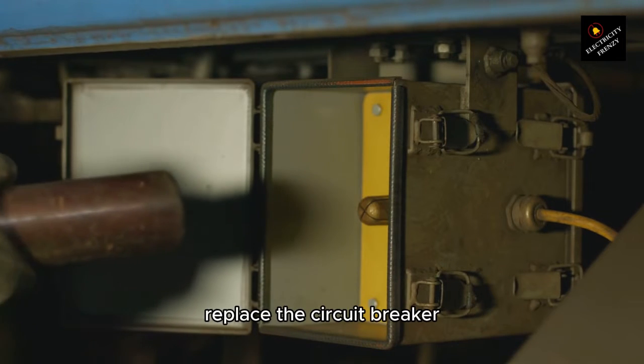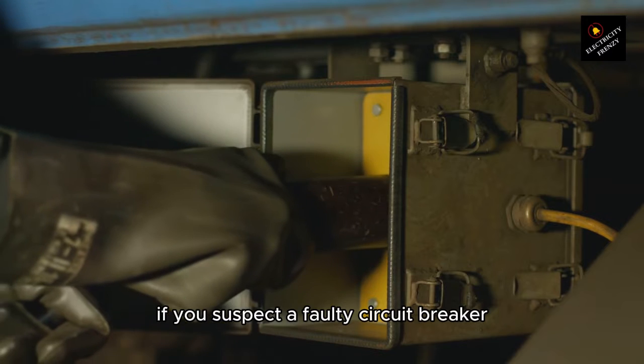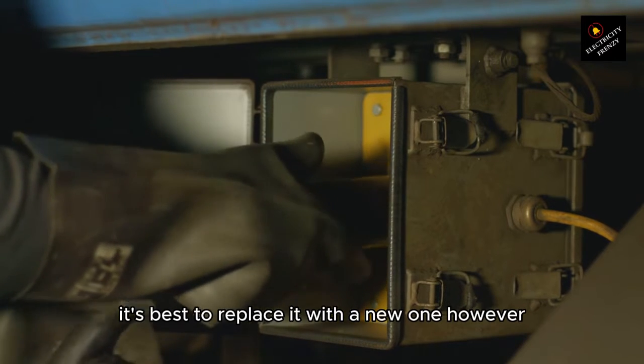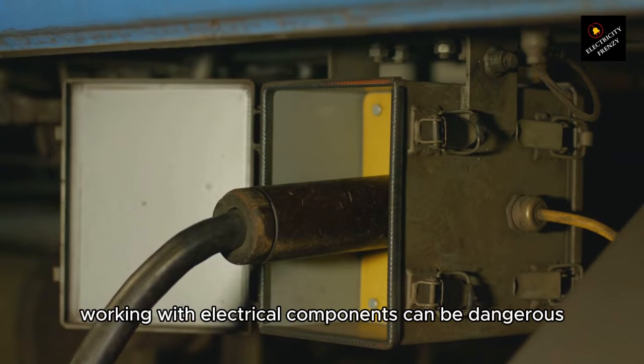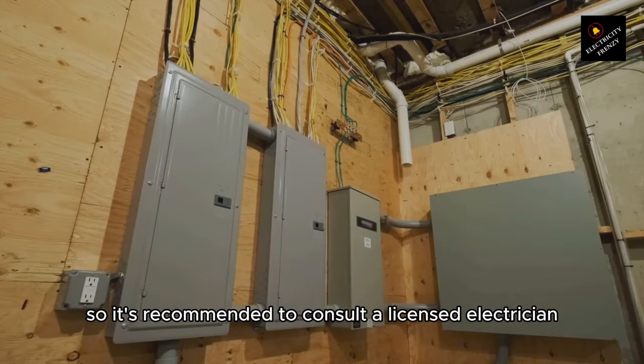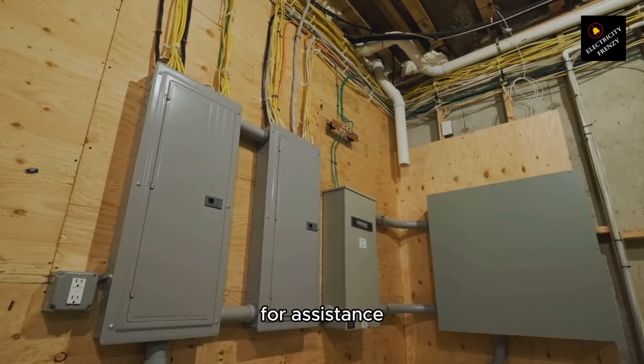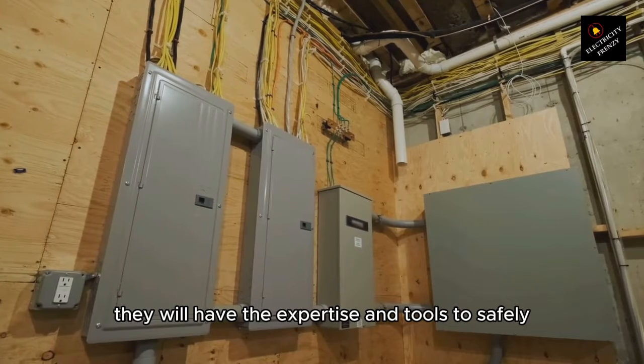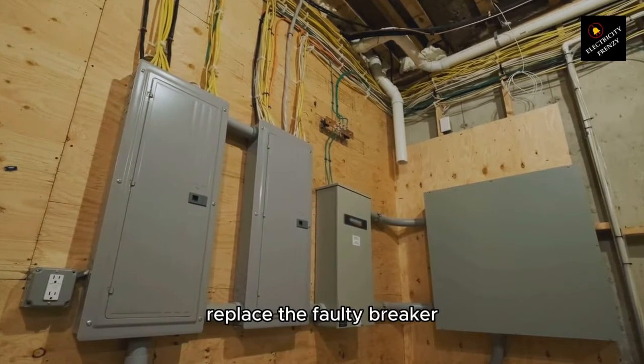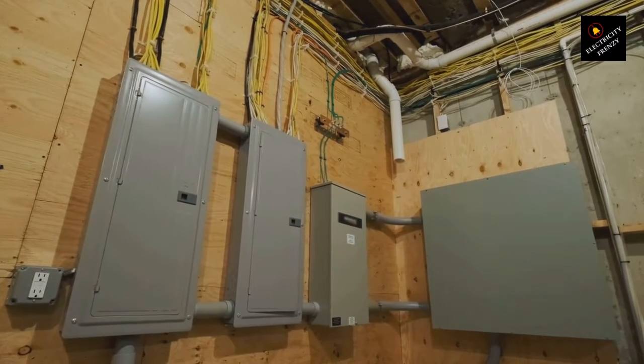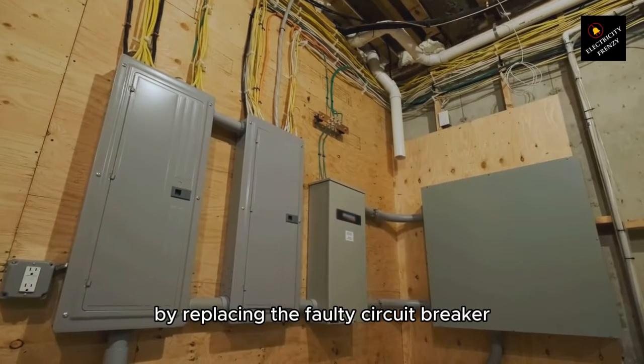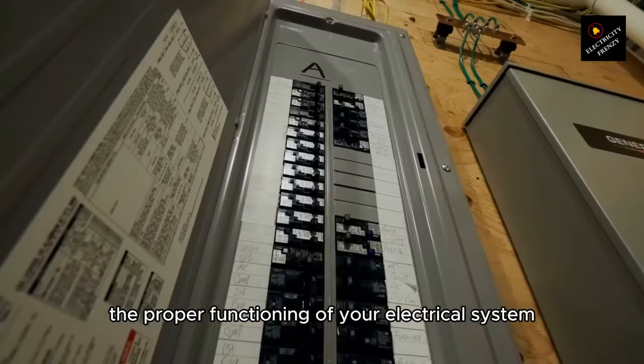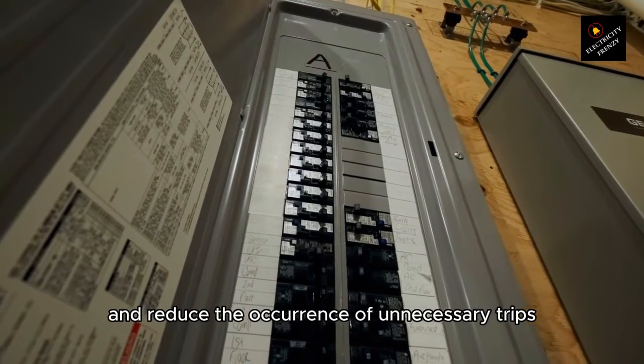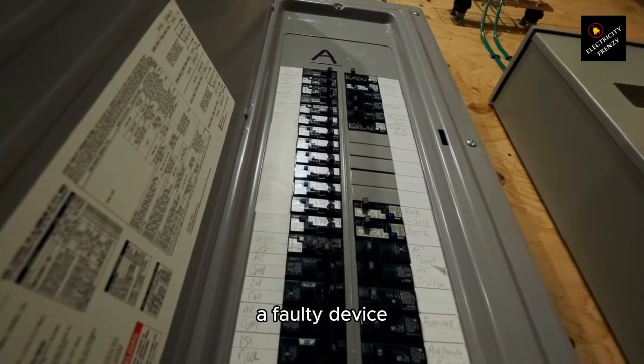Replace the circuit breaker. If you suspect a faulty circuit breaker, it's best to replace it with a new one. However, working with electrical components can be dangerous, so it's recommended to consult a licensed electrician for assistance. They will have the expertise and tools to safely replace the faulty breaker and ensure it's installed correctly. By replacing the faulty circuit breaker, you can restore the proper functioning of your electrical system and reduce the occurrence of unnecessary trips.